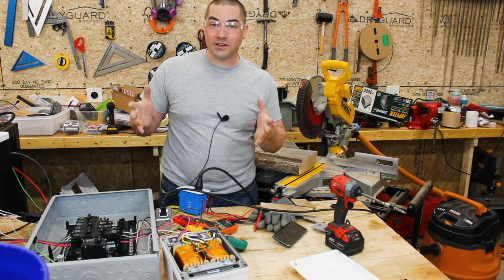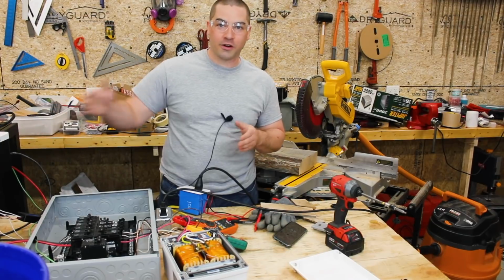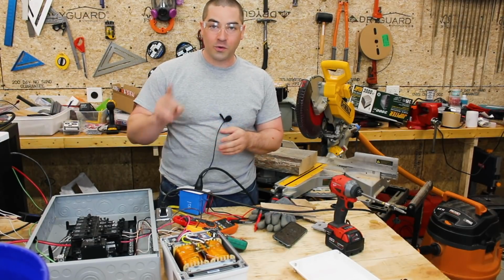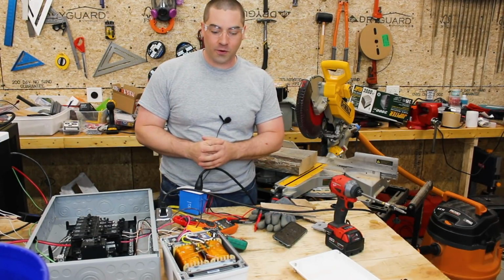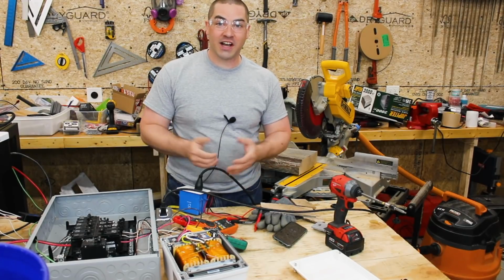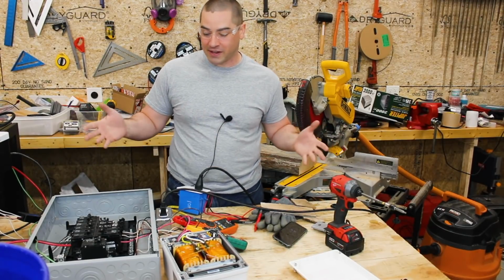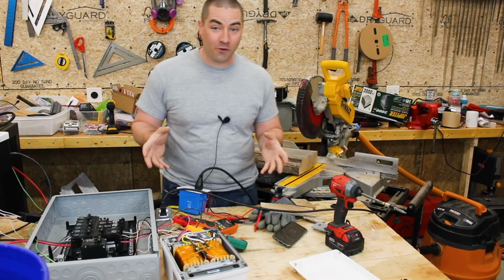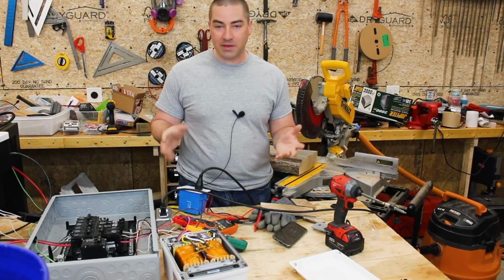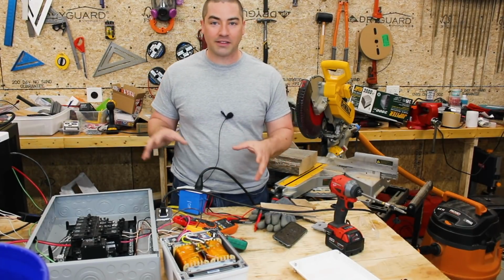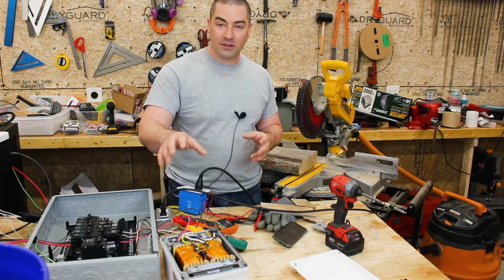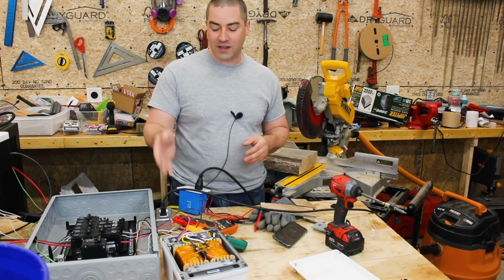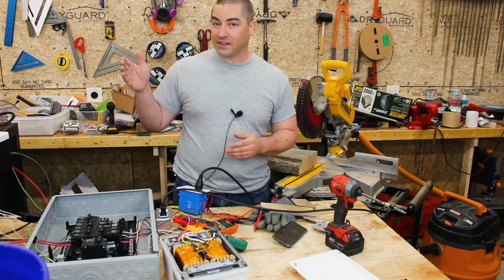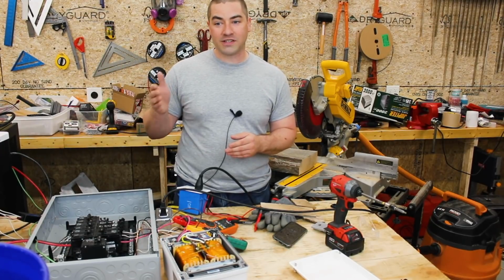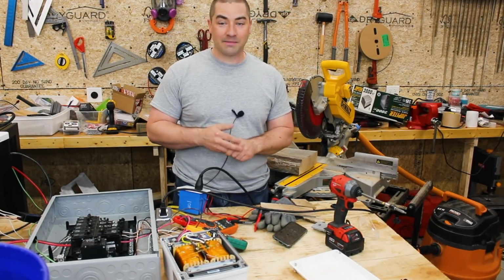This is why you can hook up multiple 240 volt inverters with just one small auto transformer. You don't need a giant auto transformer for everything. This is fairly new information for me, which is why it's so exciting. Maybe 6 months ago or so I learned about this, about how the 2 phases balance each other out and you get nothing on the neutral. So now you can buy the 240 volt inverters and add them up.